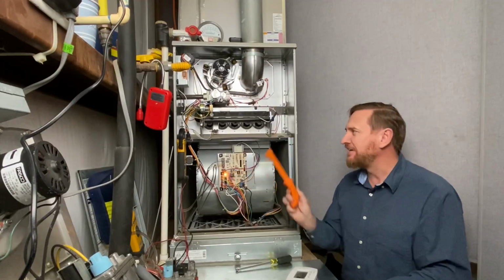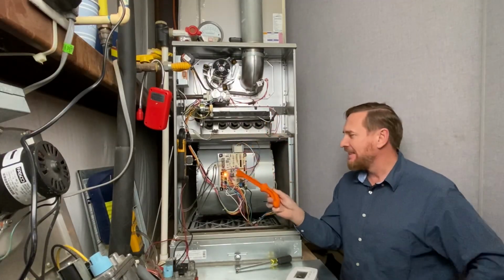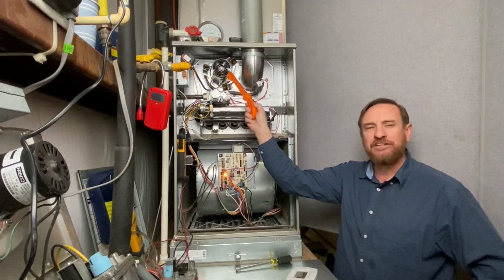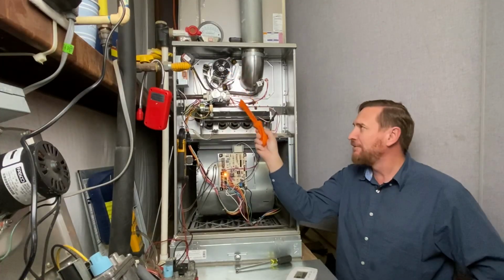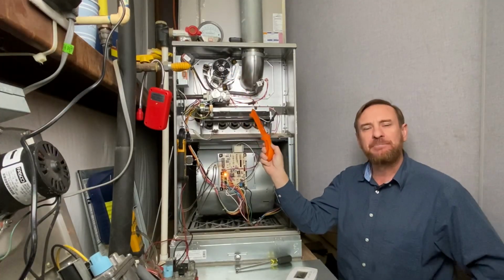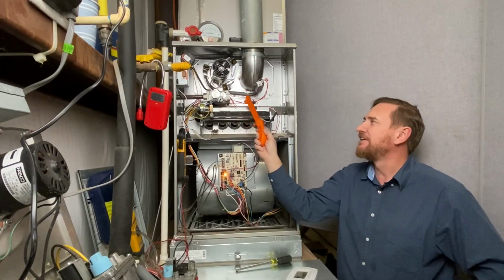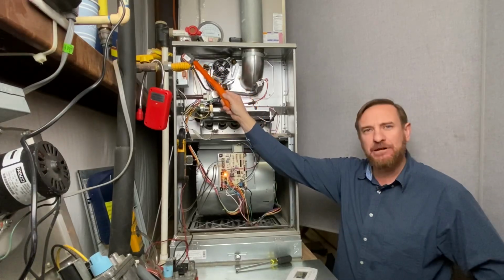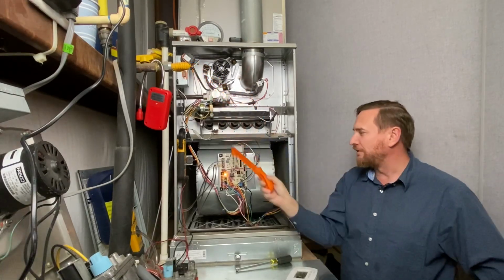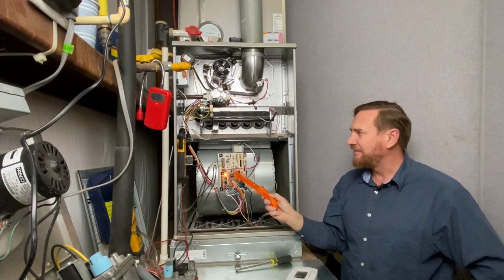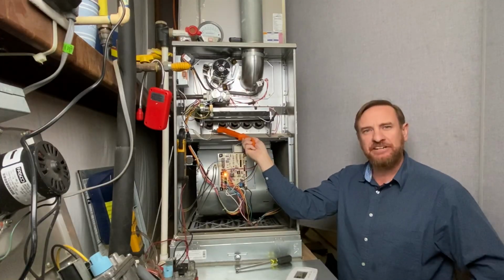The IFC does a safety check of all the safety components. The IFC then energizes the inducer draft motor, pulling a vacuum through the heat exchanger, which we call a pre-purge, about 30 seconds. It pulls a vacuum to the negative pressure switch, which closes, sends 24 volts back to the IFC. The IFC then energizes the hot surface igniter to start getting hot.